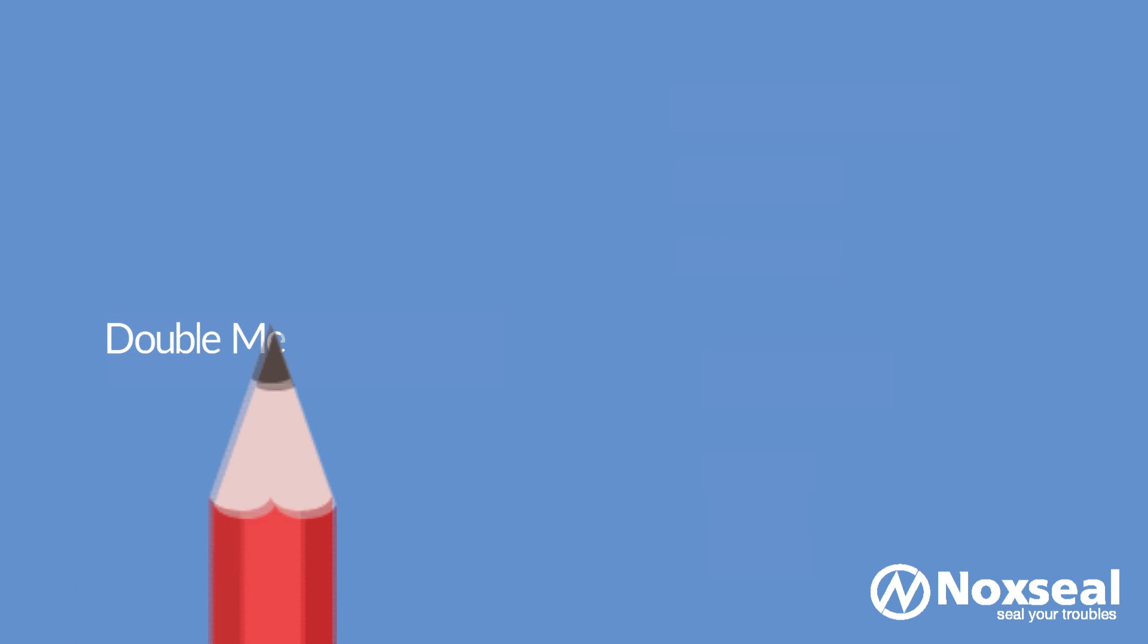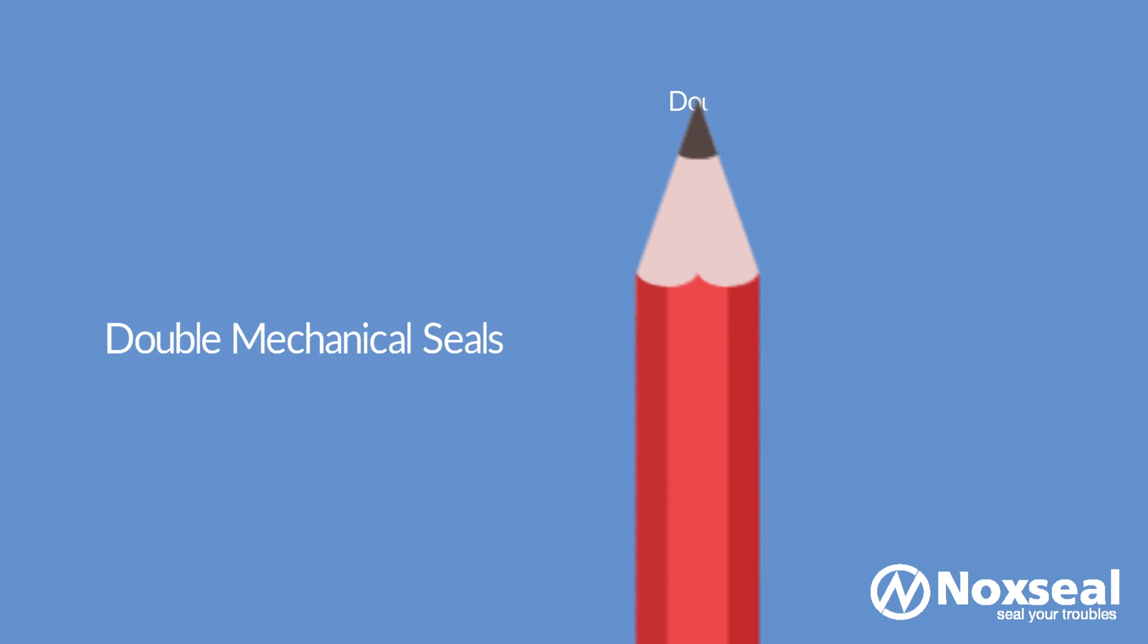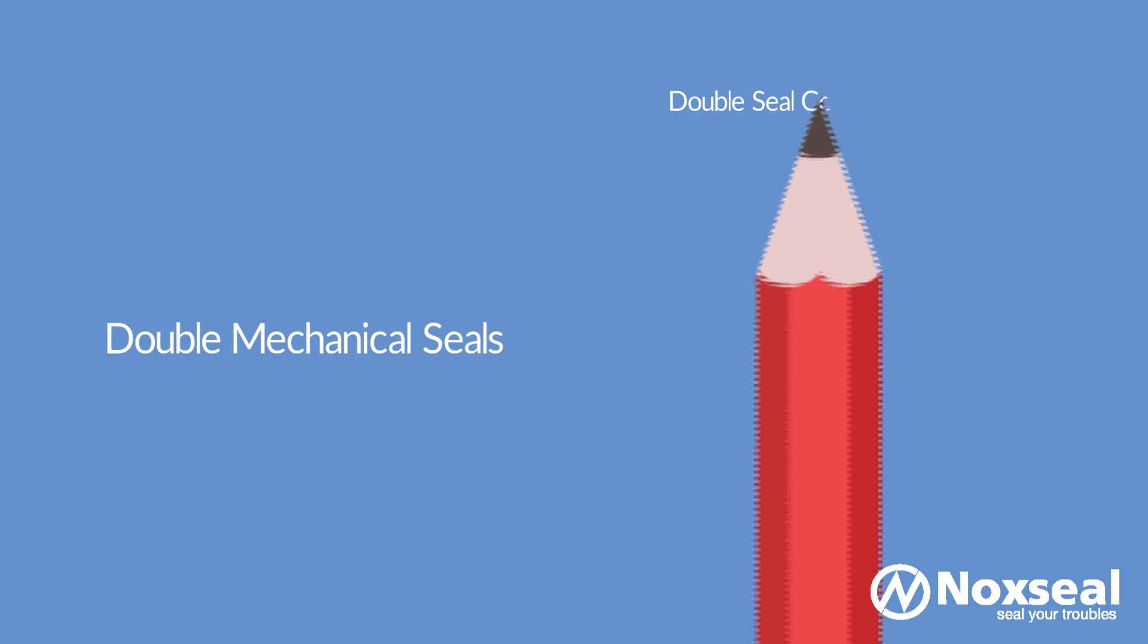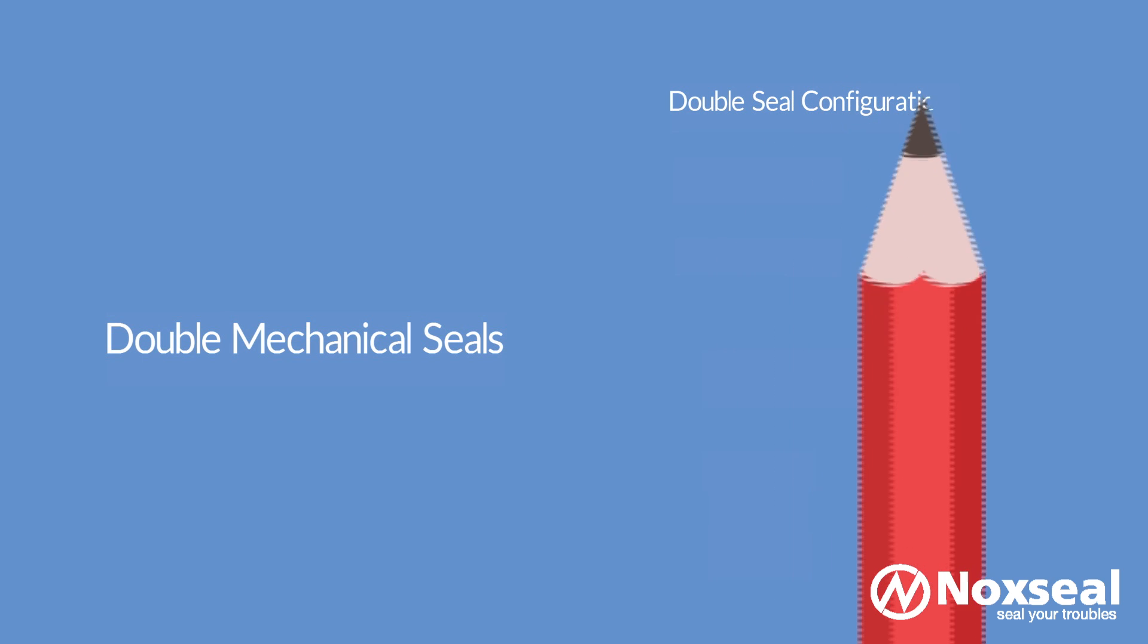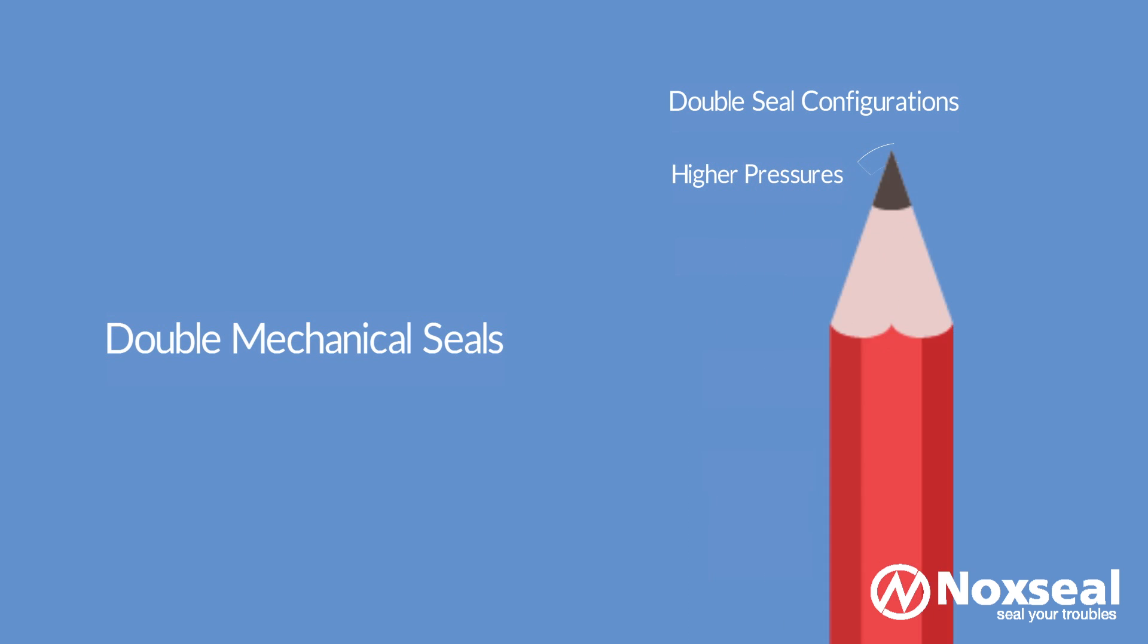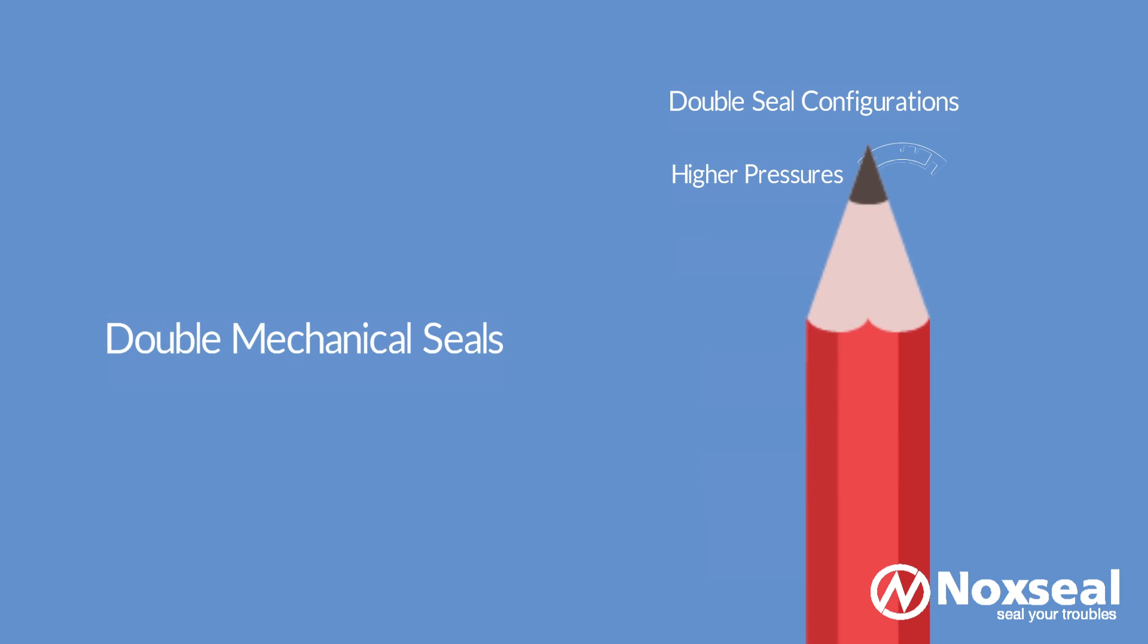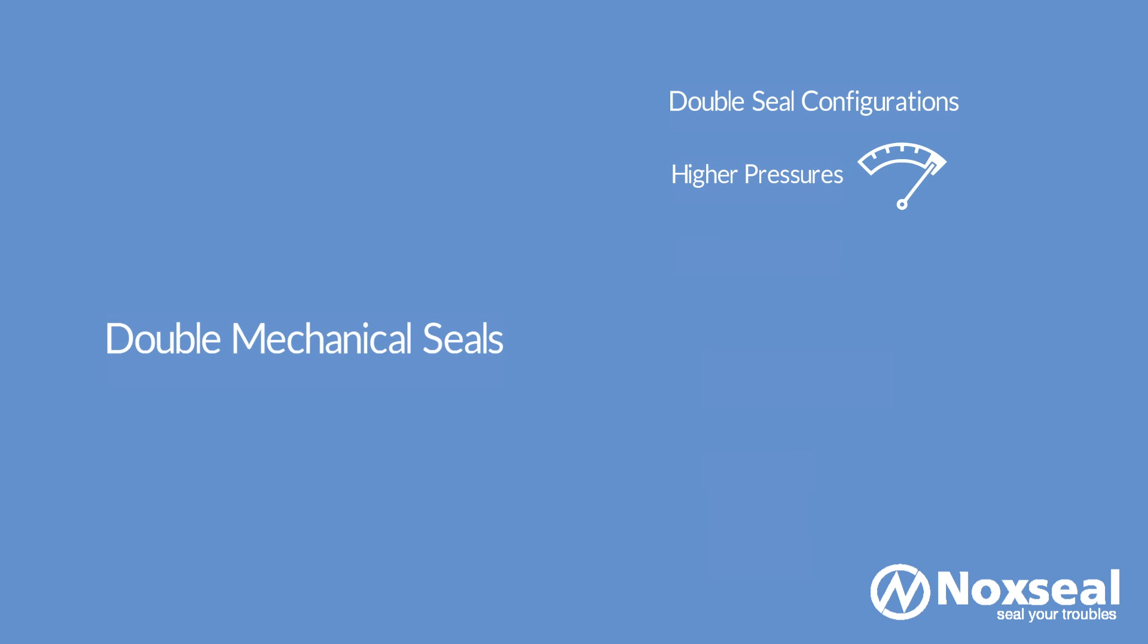Double Mechanical Seals can be designed in either tandem or double seal configurations. In a tandem seal, two independent seals are oriented in the same direction and they can withstand much higher pressures in the pump casing. They are used whenever the liquid being used poses significant safety and environmental risks.